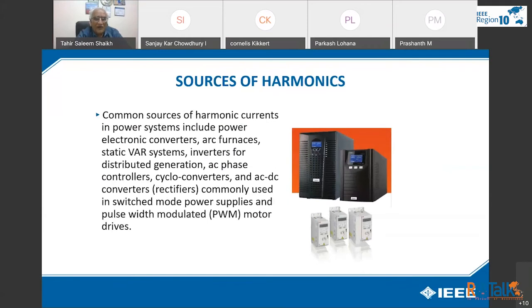Now, the common source of harmonics is non-linear loads. Non-linear loads in a power system include power electronic converters, arc furnaces, induction furnaces, static VAR systems, inverters for distributed generation, AC phase controllers, cycloconverters, AC-DC converters, rectifiers commonly used in switch mode power supplies, and pulse width modulation PWM motor drives.